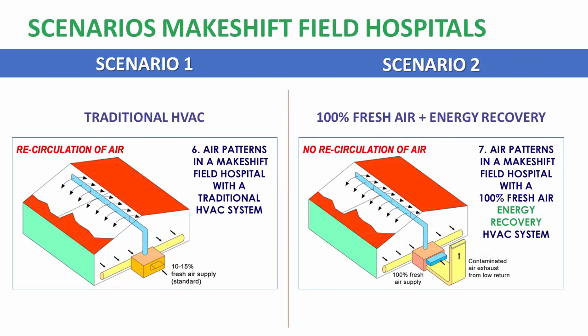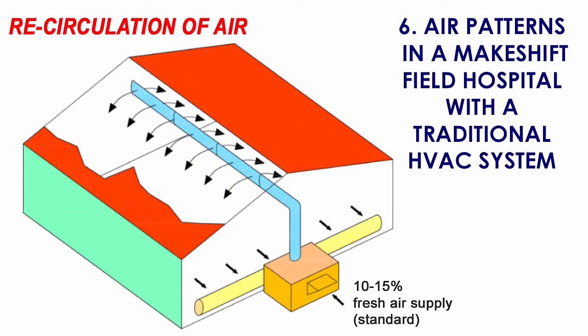Finally, let's look at two scenarios of makeshift field hospitals, starting with a hospital with a recirculating system. Here we see a traditional HVAC unit that supplies air through a duct, and in the center of the area we have a textile duct that drops the air very silently into the living space. The air comes back to the unit and gets recirculated again. This unit has only 10 to 15% fresh air, which is not ideal for COVID-19 patients, especially when they are very sick.